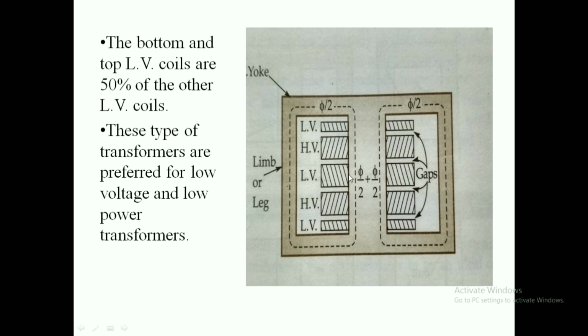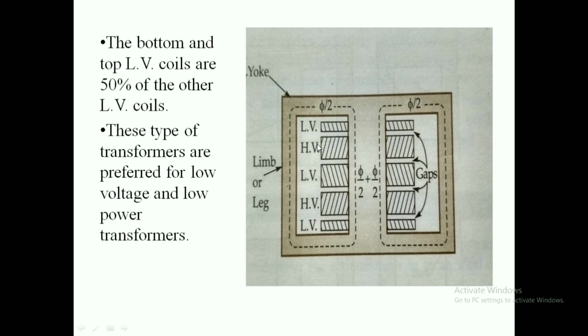Here you can see if 100 units of low voltage winding is placed and 100 units of high voltage winding is placed, then you will find that just in the middle the low voltage winding is placed, then on both sides the high voltage winding is placed, and just after it again the low voltage winding is placed. But here the specialty is, if the high voltage winding is 100 units, then this one is 50% and the lower one is 50%. But in case of low voltage winding, if the central one is 50%, then the upper and lower one are 25%.